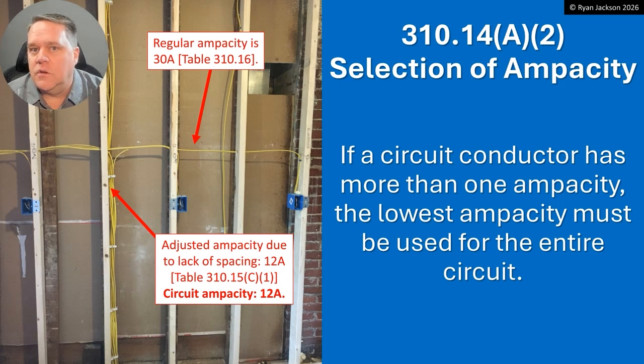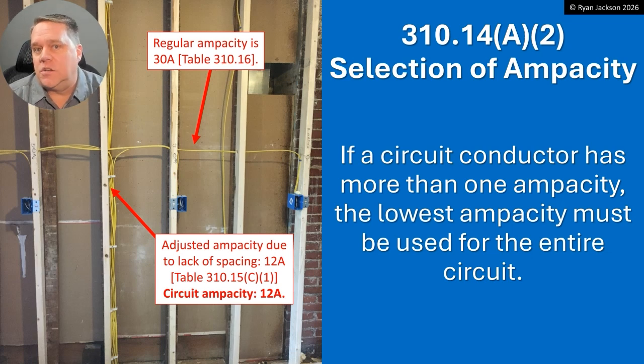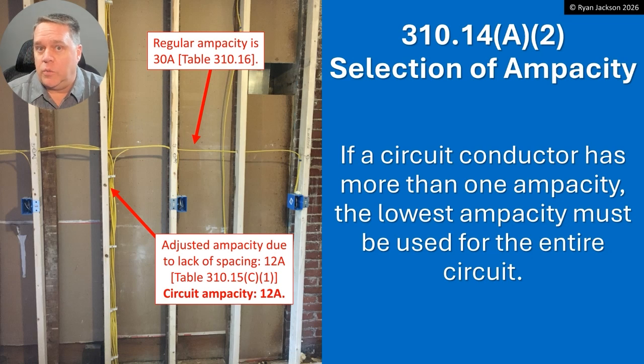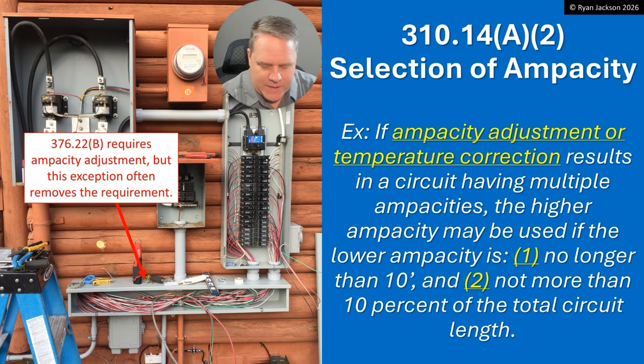You can't just look at a piece of 12-gauge THHN and say 'that's a 20-amp wire' or 'a 30-amp wire.' You have to know the conditions of use. Are you installing this on a roof in Phoenix, or are you installing it in a cellar in Alaska? Those are two different conditions of use. Are you putting it in a conduit with one other wire or a hundred other wires? Two different conditions of use — and both will change the ampacity.